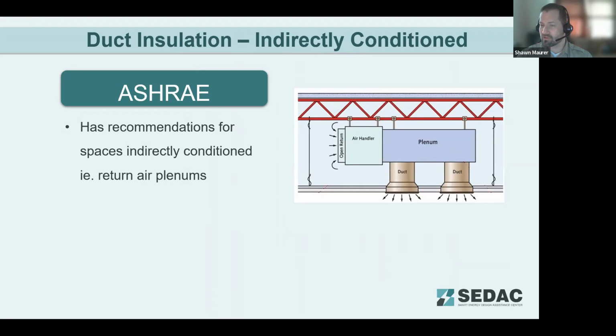Duct insulation for the most part matches the IECC: R6 for interior ducts, R8 for exterior ducts, or R12, depending on the climate zone. As ASHRAE includes indirectly conditioned spaces, there is a separate insulation requirement of R1.9 for ducts in those indirectly conditioned areas.